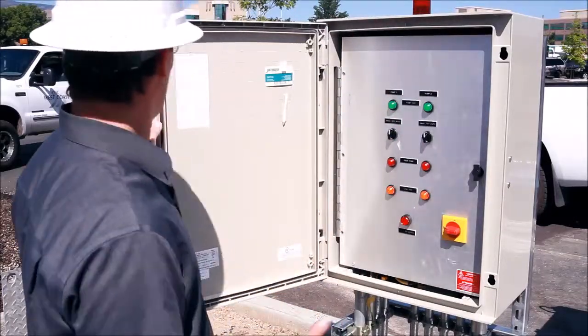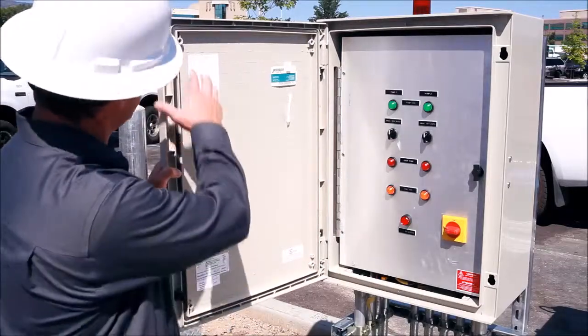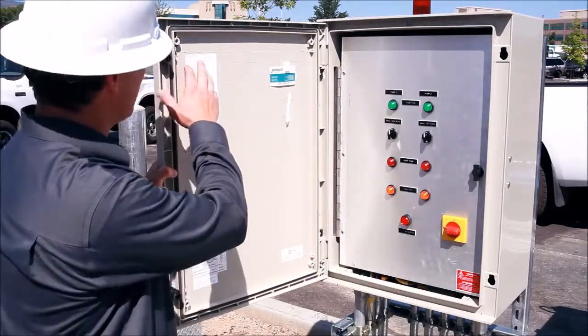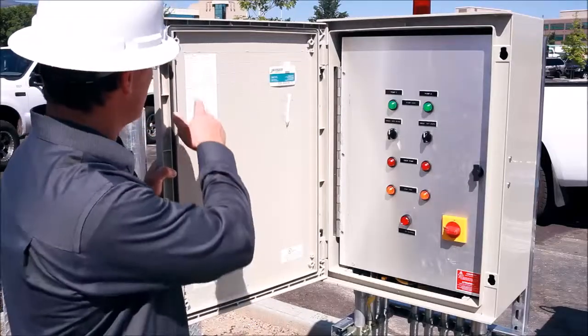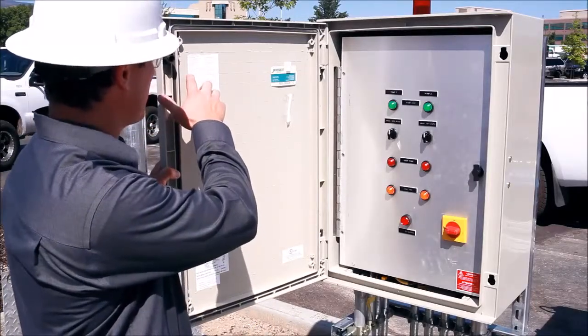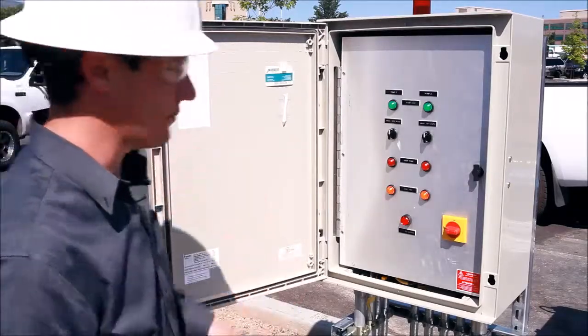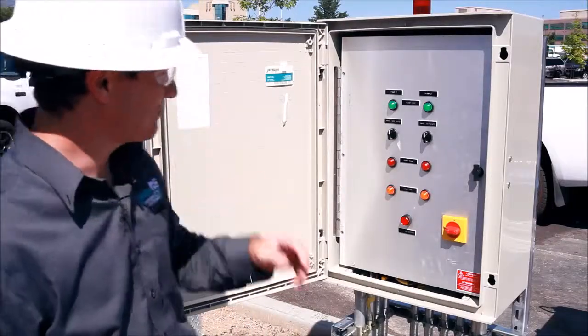So to figure out which input, for instance on this control panel, this sticker right here tells us that input 1 is the low level float, and it tells us that output number 1 is to turn pump number 1 on. So that's a little bit what's going on there.